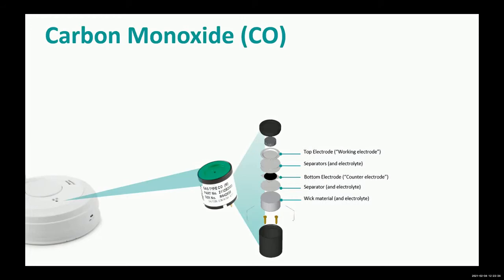Underneath that, you have a couple of electrodes and counter electrodes. You have a wick material down there at the bottom, and that wick material is very important. It has to stay at a certain moisture level. It's soaked in H2SO4, which is sulfuric acid electrolyte, and that has to retain a certain moisture level.